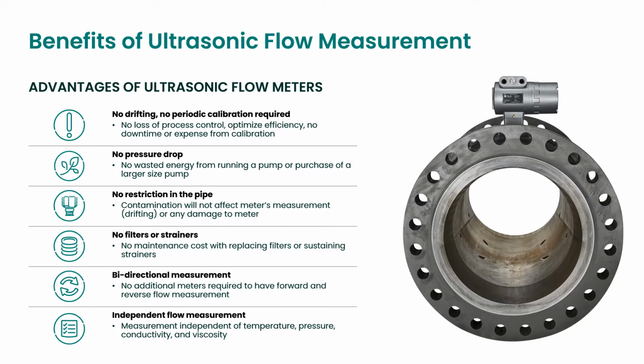Also, with ultrasonic flow meters, the sensors do not cause a pressure drop and do not waste energy. Ultrasonic meters also do not have a restriction in the pipe requiring filters or strainers. Contamination within the fluid and pipe could damage other flow meter technologies, causing drifting measurements, periodic calibration, or worst case, replacement of the meters. Ultrasonic flow meters are bidirectional, which can save you money if your process flows in both directions, such as a loading and unloading type application. Ultrasonic flow measurement is independent of temperature, pressure, viscosity, and conductivity. Therefore, an ultrasonic flow meter can be designed for different fluids and process conditions without significant impact to the measurement and process control.